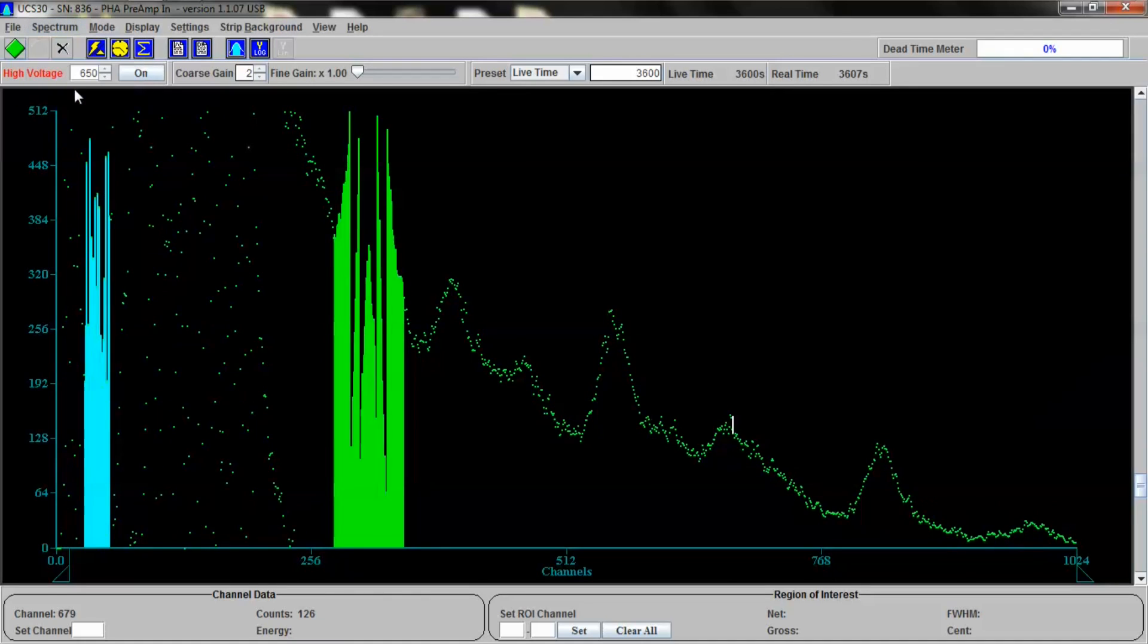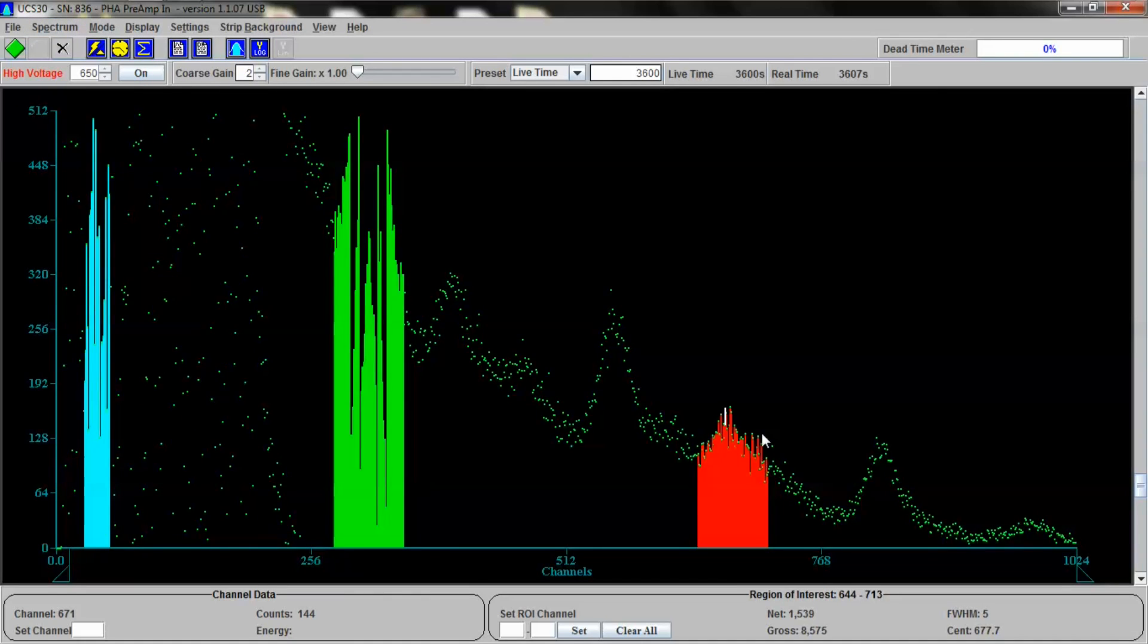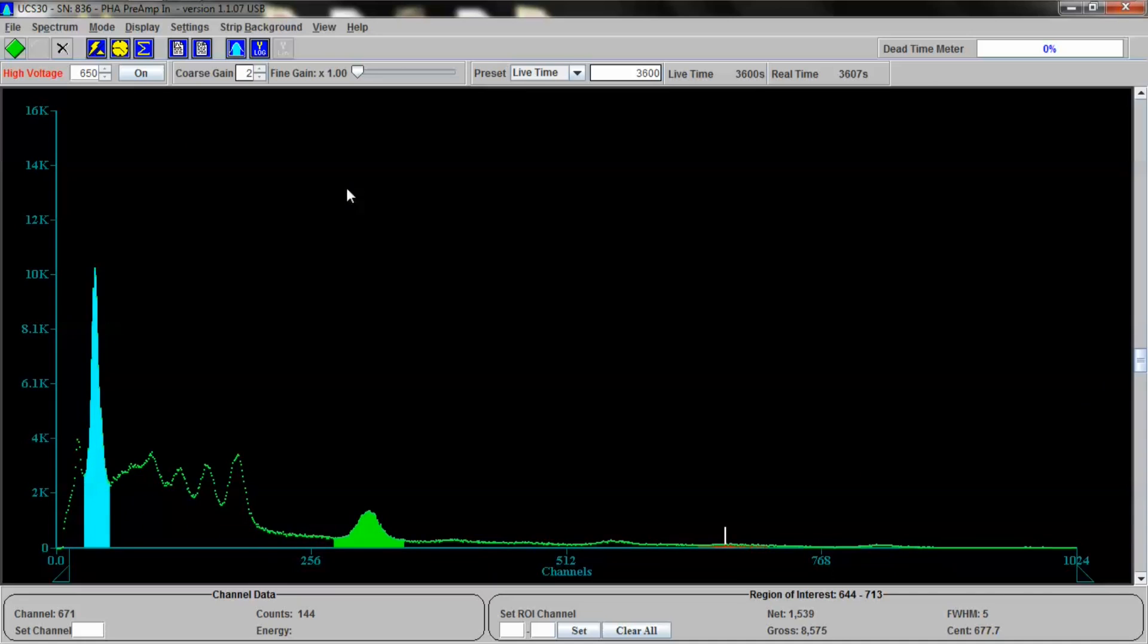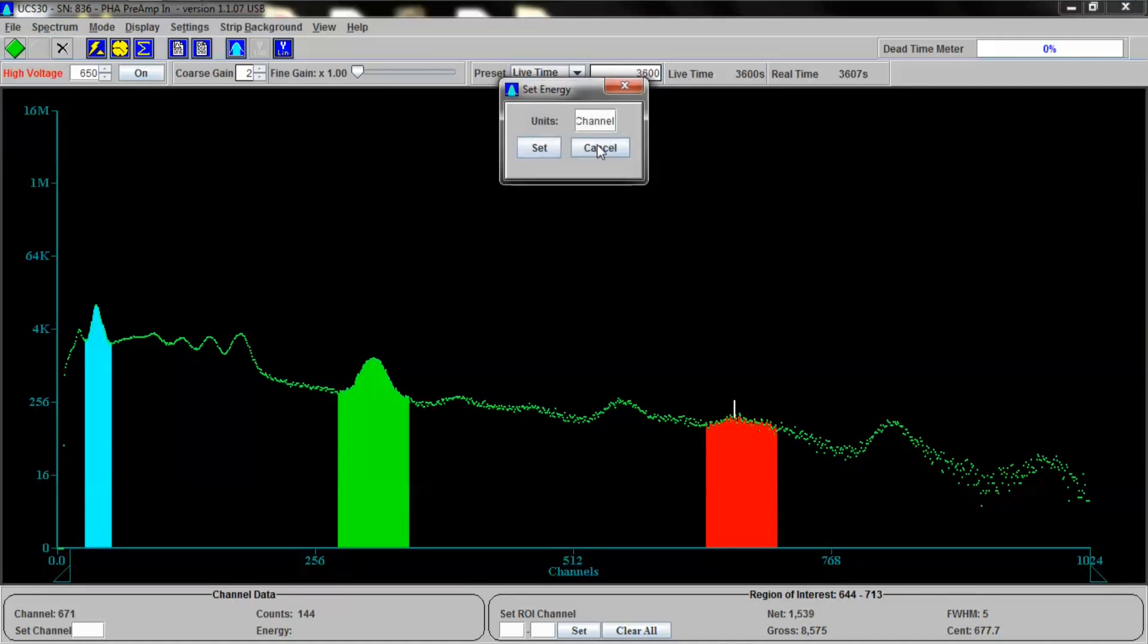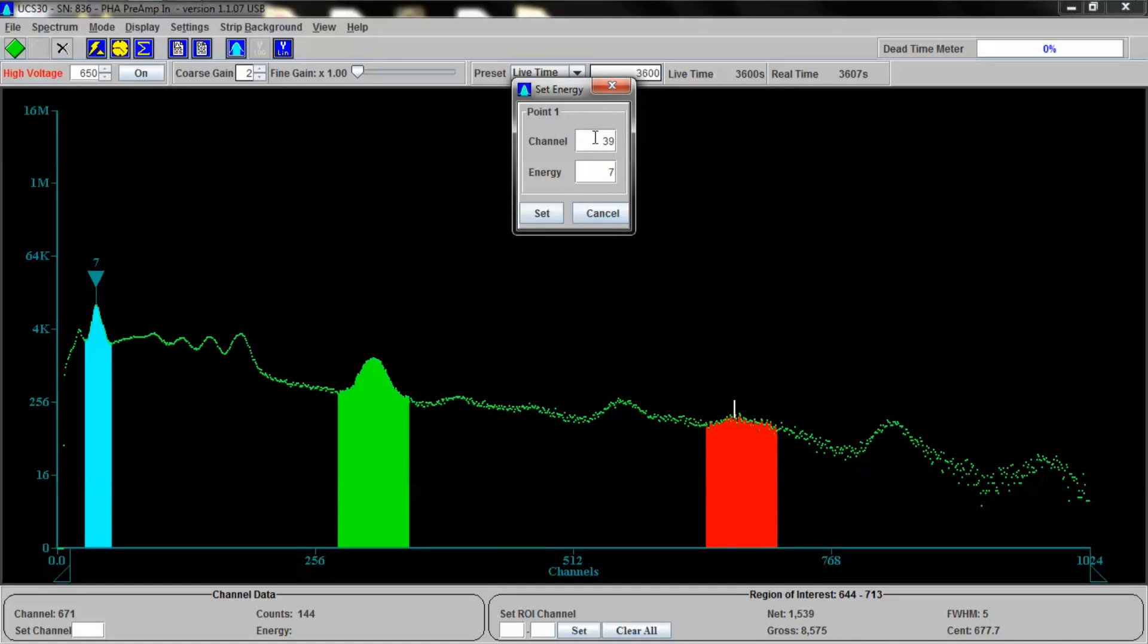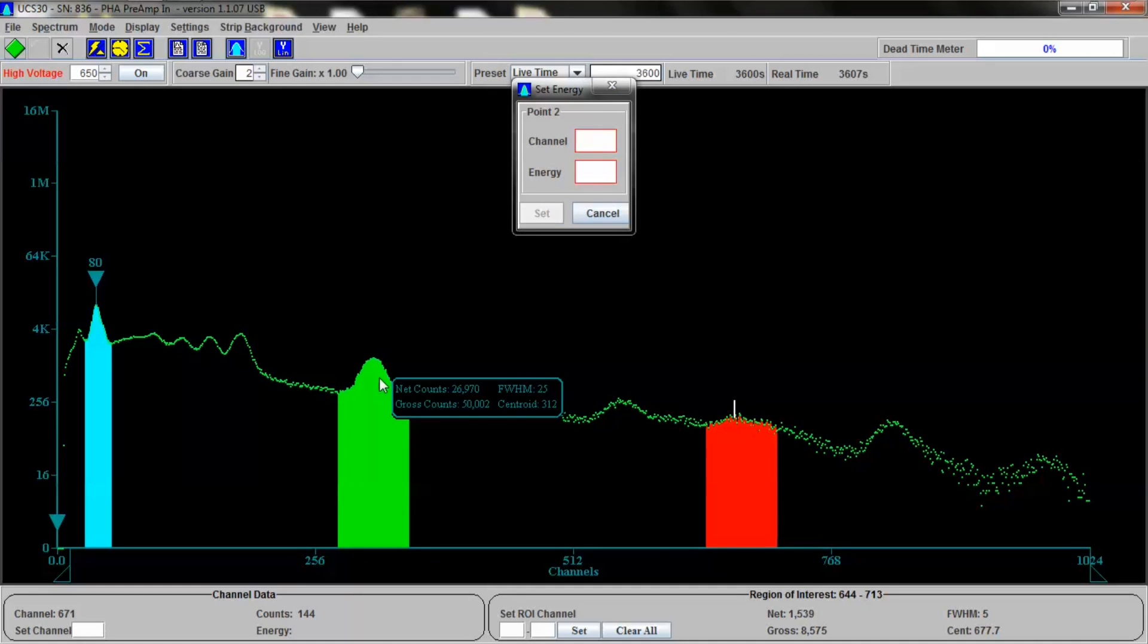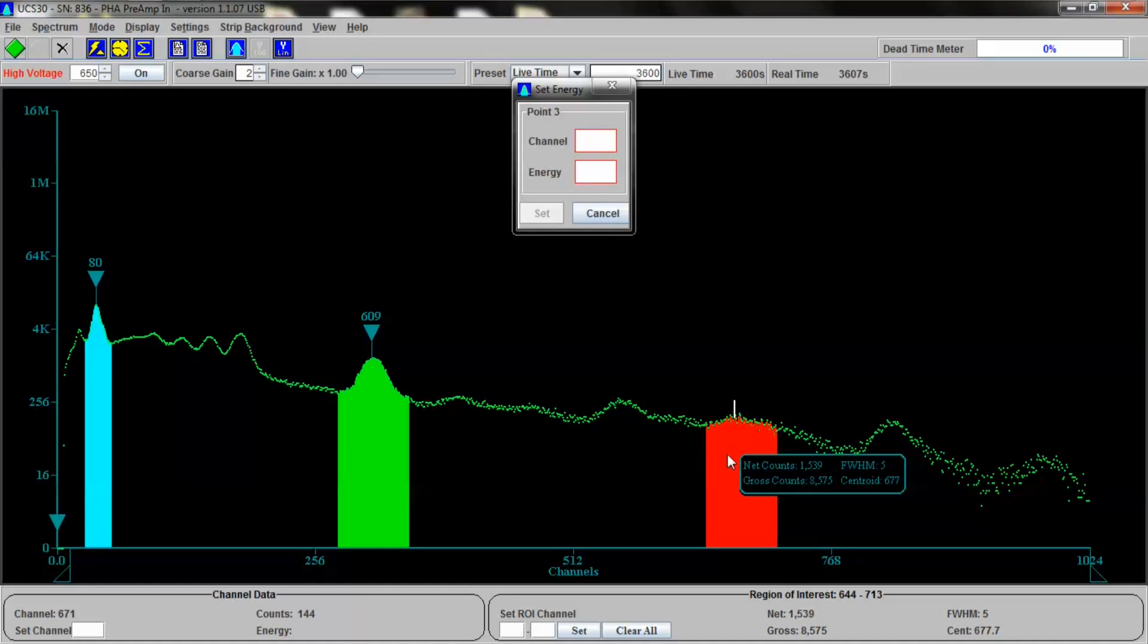Anyway, now that we've gotten the data, and I probably could have gotten this in about 30 seconds. This is a pretty strong system. Let's highlight the x-ray fluorescence. We'll highlight the bismuth-214, and put this in the linear mode, where you can fly down here. We get the potassium-40. Boom. And now we can do a three-point calibration mapping energy to channel, which is also kind of useful. So this takes a little while, but I'm doing it really fast for you, because magic!